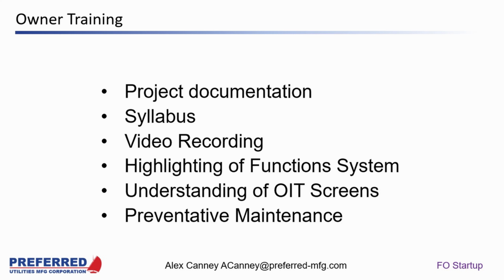Same thing with level on the day tanks - this is the screen you go to for that. If you have a problem, you can go into the IO screen and see the milliamps for what you're actually getting as far as a level, and verify whether it's reading correctly or not through that.